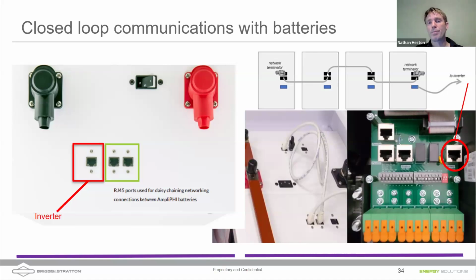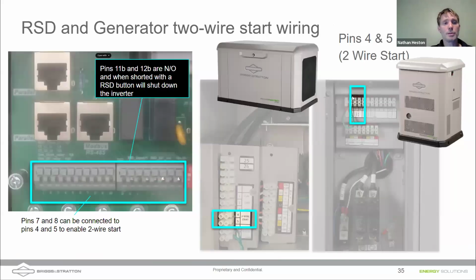So we'll go daisy chain battery to battery. It does not matter which battery port you use. They're both symmetrical. Battery to battery, battery to battery, and then terminating resistor. And then off that last battery, actually, it doesn't matter which battery, we will run from the device port to the inverter. I'm showing here where that comes in. There's a CAN bus port on the center of the Sol-Ark 15k. And so that's how you wire the communications of our batteries into the Sol-Ark 15k. Once you do that, programming becomes much simpler.